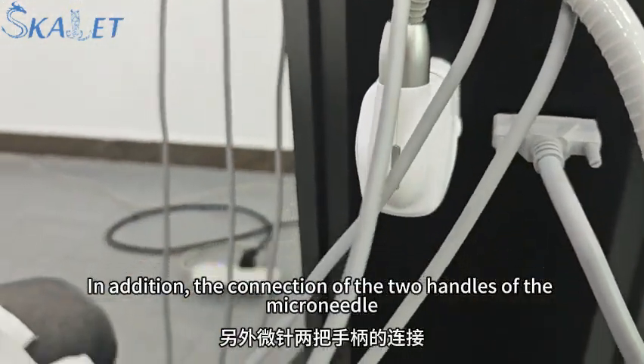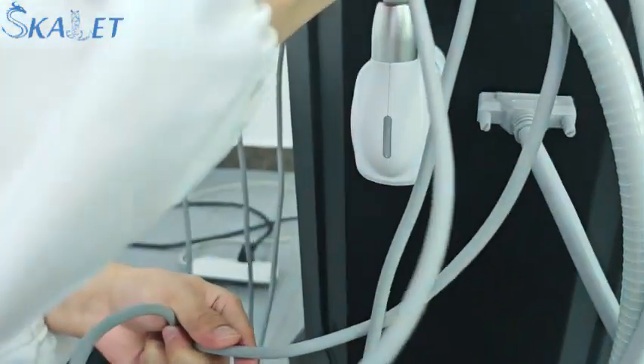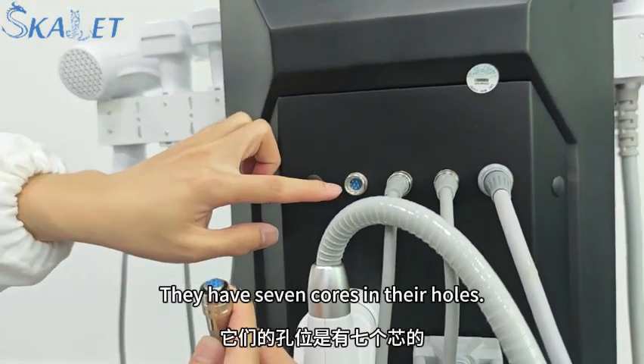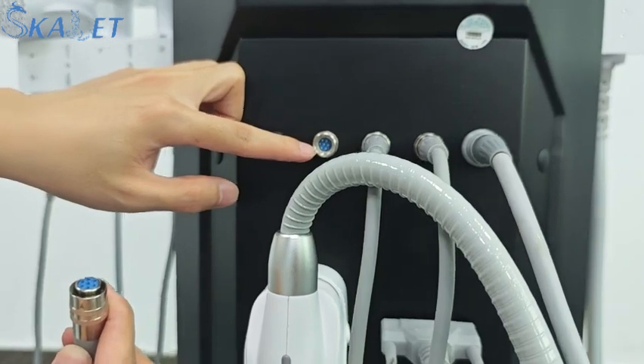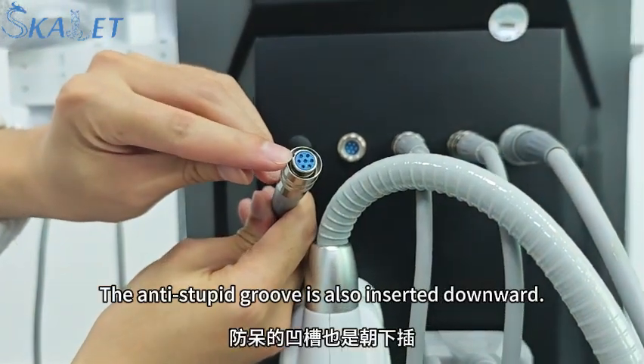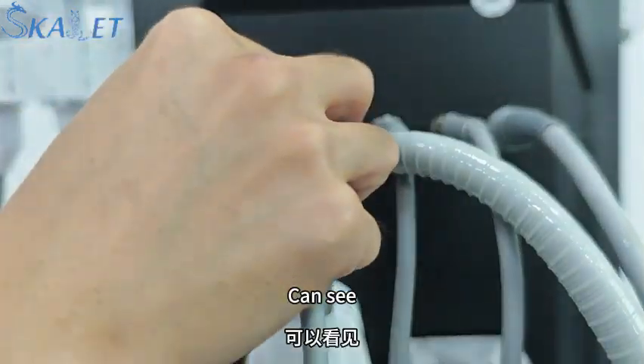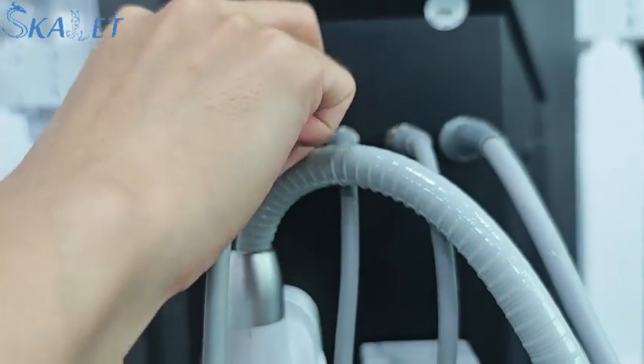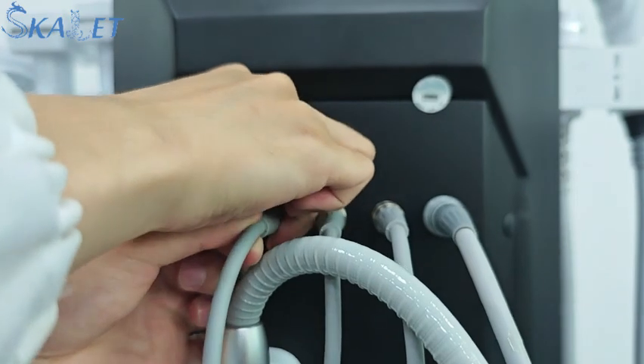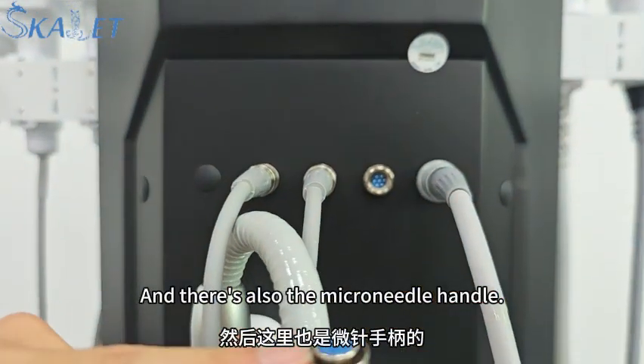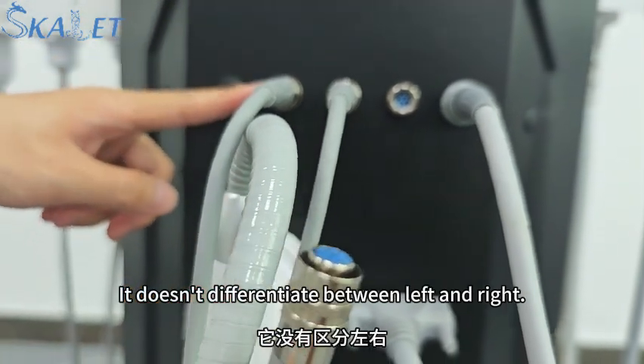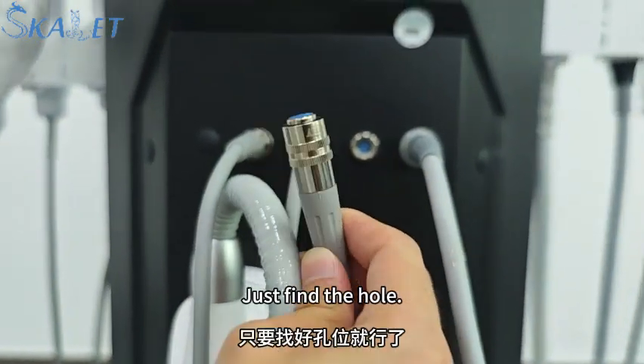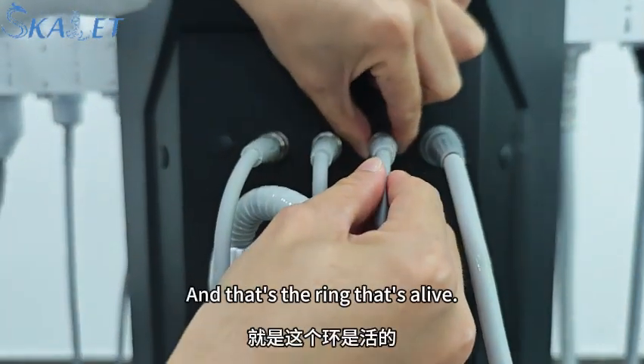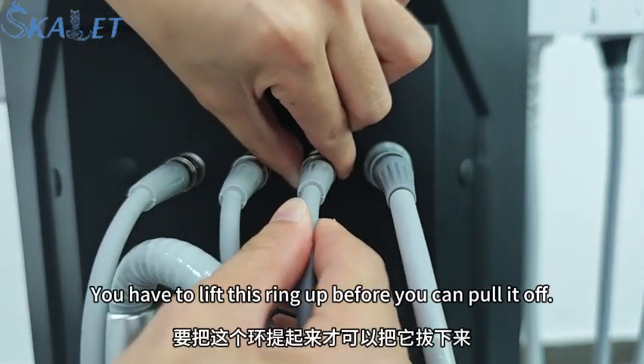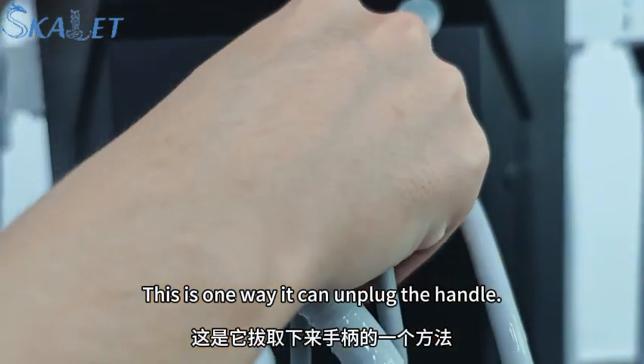In addition, the connection of the 2 microneedle handles. These are the 2 microneedle handles. They have 7 cores in their holes. The anti-mistake groove is also inserted downward. These two microneedle handles don't differentiate between left and right, so we can insert either into both holes. Just find the hole. If we want to remove the handle, it has an inner ring. When we pick it up, you have to lift this ring up before you can pull it off. This is one way to unplug the handle.